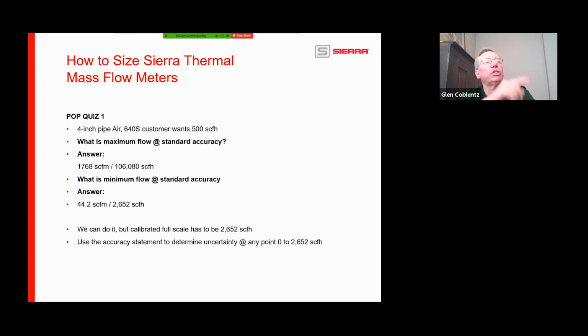The minimum full scale on a 640S is what? It's 500. So the minimum full scale would have to be this. He wants to measure this. What's the accuracy? This is a 1% plus 0.5% of full scale device. He's going to have a big uncertainty right here. Okay.